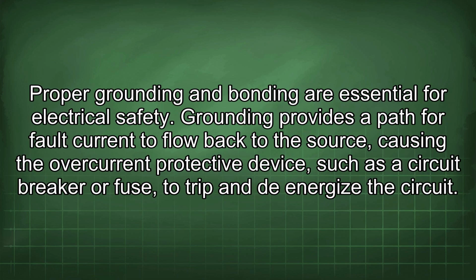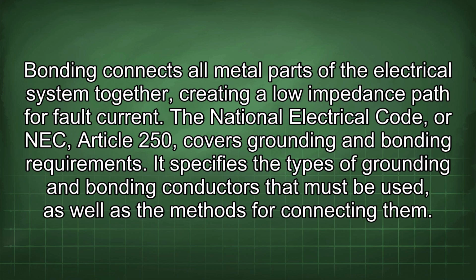Proper grounding and bonding are essential for electrical safety. Grounding provides a path for fault current to flow back to the source, causing the overcurrent protective device, such as a circuit breaker or fuse, to trip and de-energize the circuit. Bonding connects all metal parts of the electrical system together, creating a low impedance path for fault current.